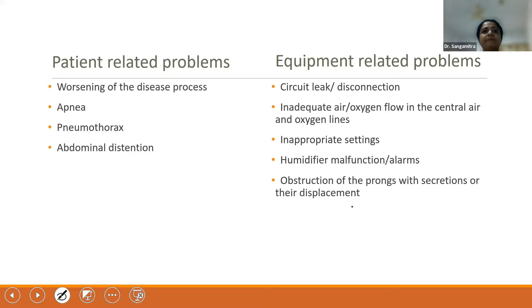Then the next one is inadequate air and oxygen flow in the air lines or oxygen lines, which is very, very common and the main bottleneck nowadays in most units. And the next is inappropriate settings. Suppose the baby has severe retractions and requires CPAP of 6 or 7, you might have started just on CPAP of 4. So these inappropriate settings, humidifier malfunctions and alarms, and sometimes the prongs might have been obstructed or displaced at the level of the interface, so CPAP might not be delivering. So these are the equipment-related problems that you need to be aware of, so that you first look at them when you feel the CPAP is not working or the baby is failing CPAP.